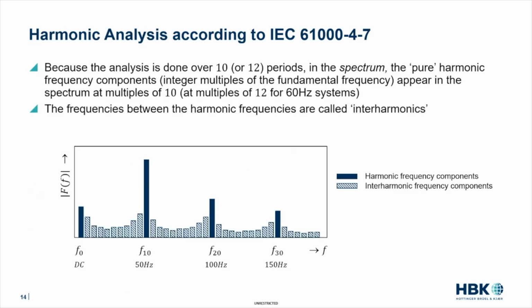Well, okay, we're diving into a bit more detail. What the standard says is that we have to take 10 or 12 periods. But if we do that and we go to the frequency domain, then we get a spectrum. And what you then see in the frequency domain is that what you may call the pure harmonics appear at multiples of 10, or 12, of your frequency components. So if you have a time signal of 200 milliseconds, then the frequency resolution in your spectrum is 5 hertz. So if you want to go from 0 hertz, so DC, to 50 hertz, then you have to make 10 frequency steps. And that is shown in this picture here. So if you take 10 periods in your time signal, then you get a spectrum that looks something like this.